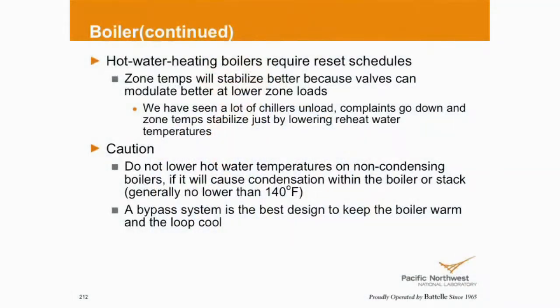That's great. So some of the things that we talk about with boilers, again, the cautionary bullet there, if you don't have condensing boilers, you are limited. We heard 160. We have 3 large boilers that we rarely run below 180. I hate to say that. Bypass mixing loop is a great option if it's designed by the engineer, where you can keep the boilers warm and drop the temperature on the loop.